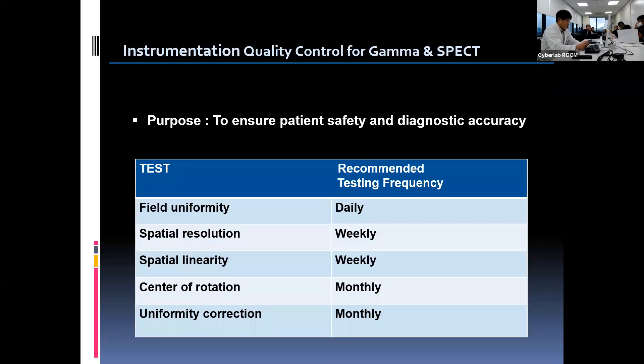Let's move on to today's subject. The quality control testing on instruments should be performed thoroughly to ensure patient safety, efficiency, and diagnostic accuracy. Through the QC procedure, we can identify equipment problems before they affect clinical patient studies, and it is important to verify that all camera calibration is up to date. This table shows the list of major QC tests and optimal testing frequency.